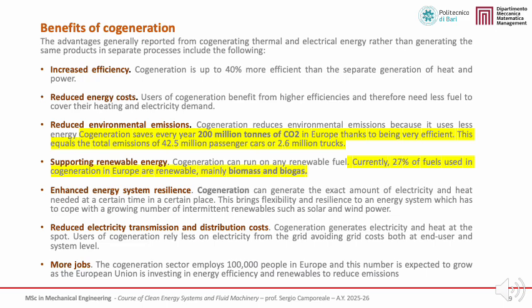In this slide, we summarize the main benefits of cogeneration compared with the separate production of electricity and heat. The first key advantage is increased efficiency. By producing electricity and useful heat simultaneously, cogeneration systems can be up to 40% more efficient than separate generation, significantly reducing overall energy losses. Higher efficiency directly translates into lower energy costs. Because less fuel is required to meet the same electrical and thermal demand, cogeneration users benefit from reduced operating expenses.